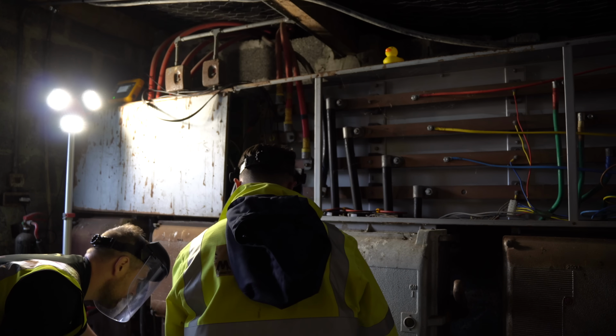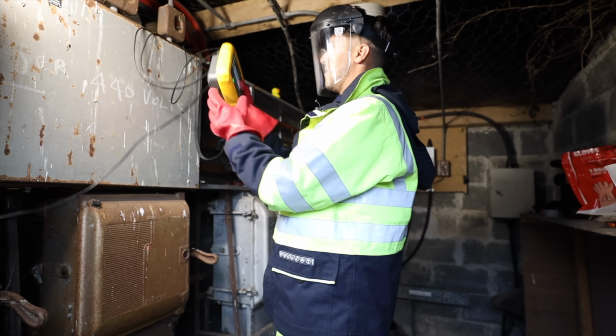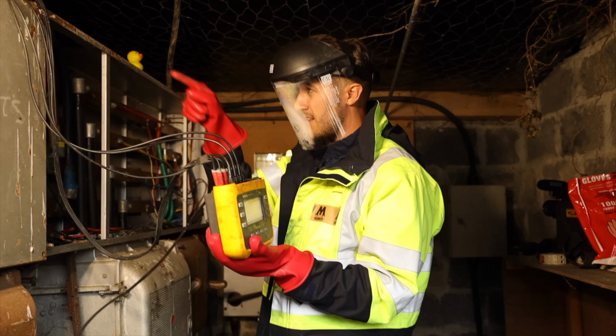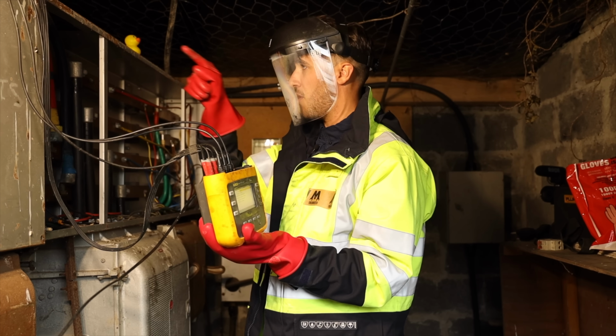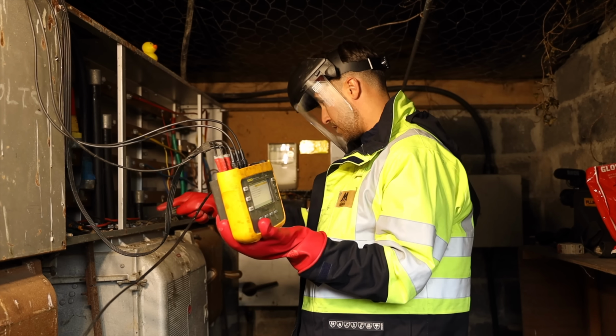Our power analyzer, or data logger, is up here. It's connected through crocodile clips onto the bus bar, and also little CT clamps around each one of the incoming tails. See these crocodile clips here, clipped onto each phase and neutral, and then you've got these CT clamps rolled around each one of the phases. These red cables are going to go out to the generator supply, so they're not actually HV - this is all LV in here, meaning it's below 1000 volts.